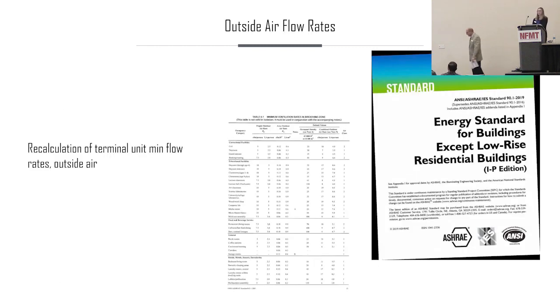So another way to basically tune your building is to consider what outside airflow rates you are bringing into your building. A lot of times the spaces may change, and per the ASHRAE 62.1 standard, different space types require different types of outside airflow rates. This is one of our examples, but if you have a wood shop that then got turned into a storage room, you don't really need more outside air for that space. You could actually bring in less. So that's one way. If your space types change, then refer back to ASHRAE 62.1 and see, okay, what outside air do I need in each of these spaces? And you could potentially bring in less for your air handler to have to condition.